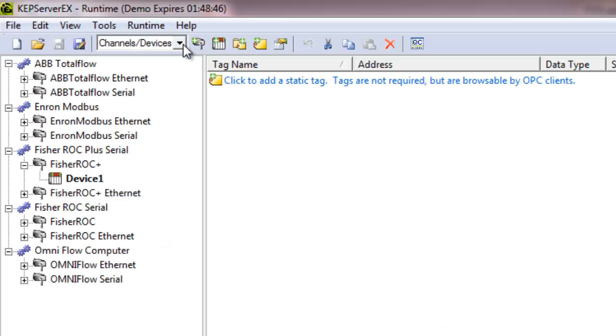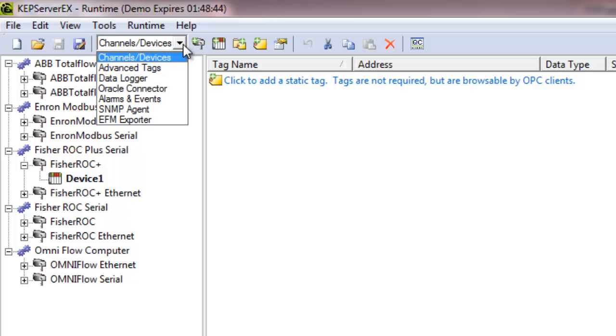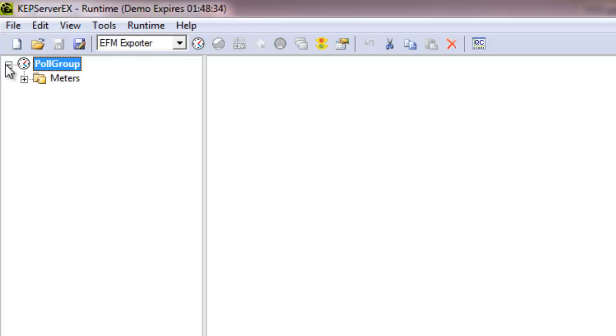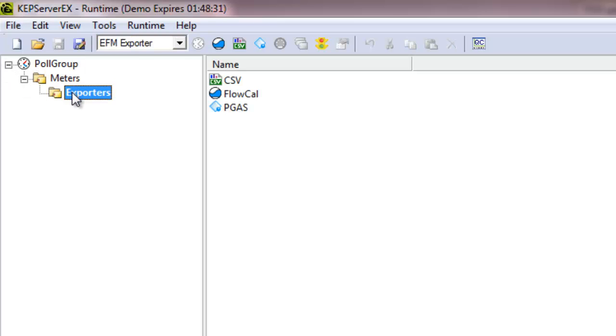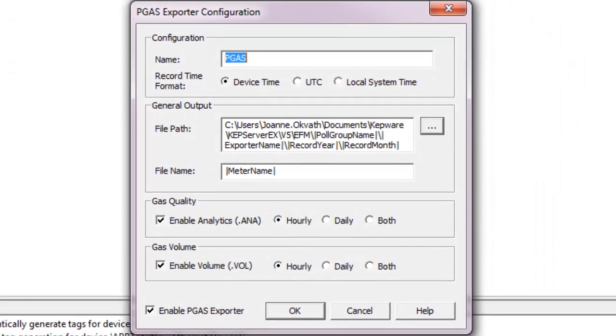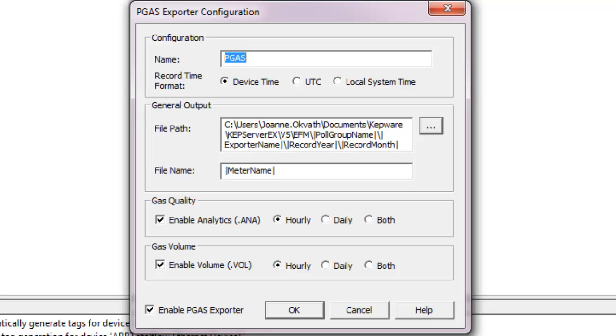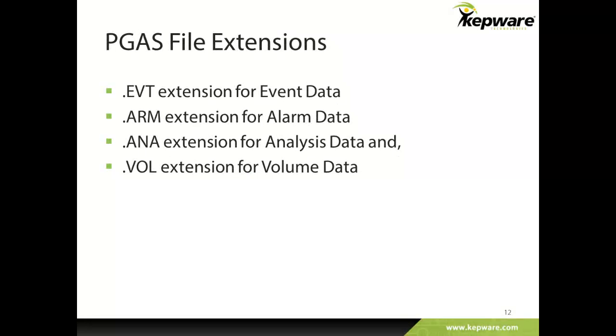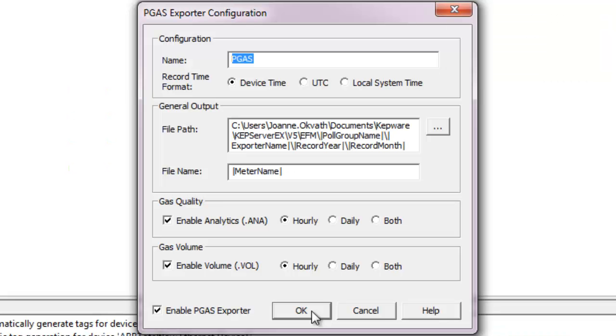Now let's go to the EFM exporter plug-in to explore the added functionality for reporting measurement data. Go to the View selector and select EFM exporter. Similar to FlowCal, PGAS is a gas accounting software product that customers may use. The EFM exporter supports up to PGAS V8 formats. PGAS uses separate output files for each data type, with different extensions for event, alarm, analysis, and volume data.